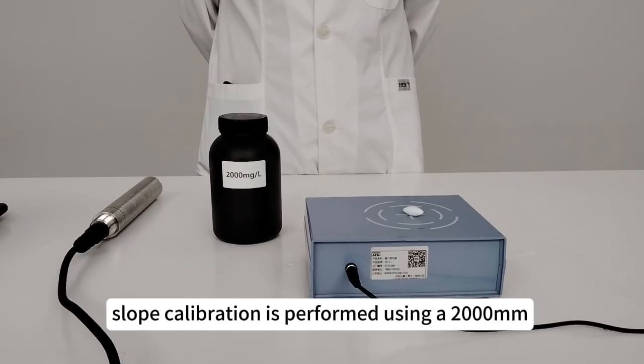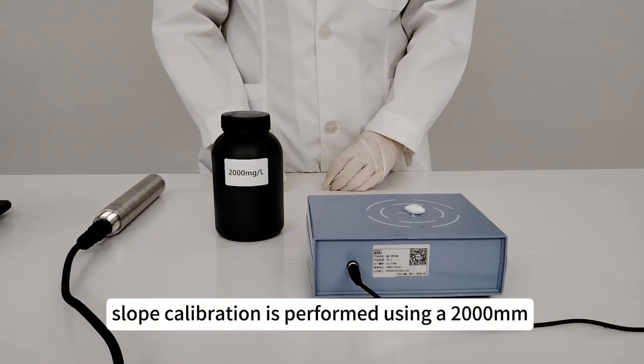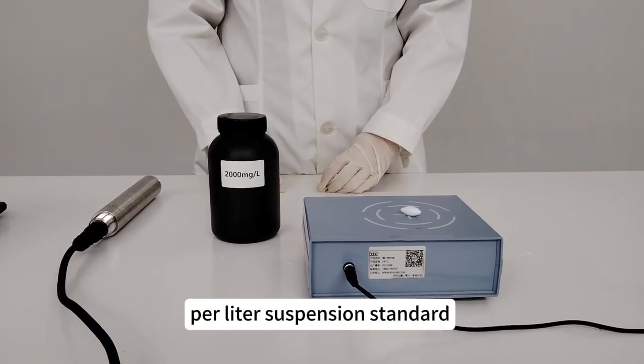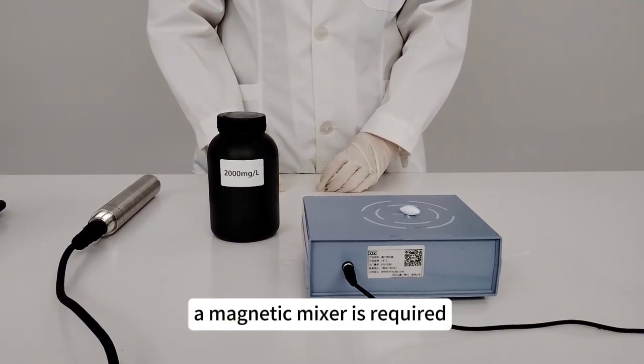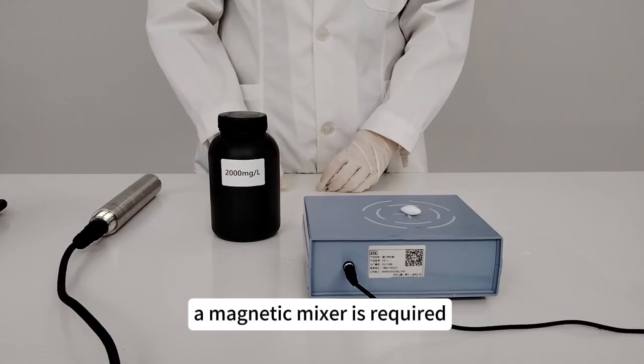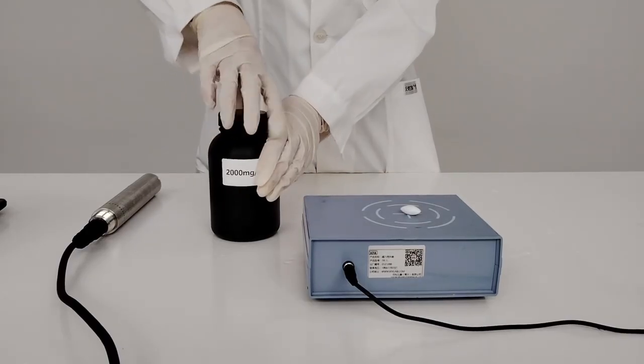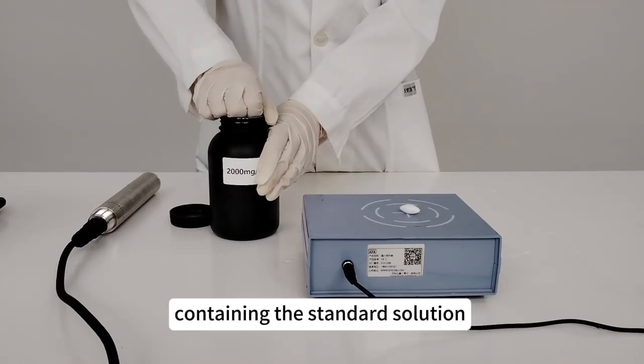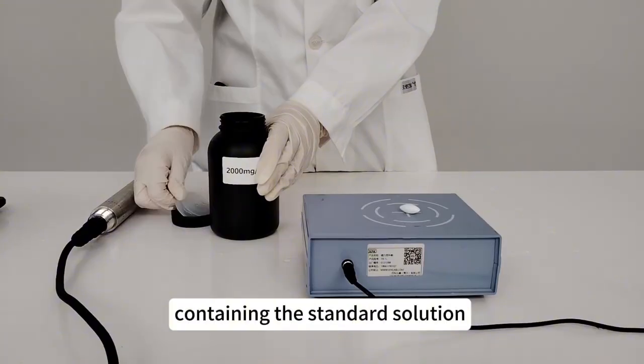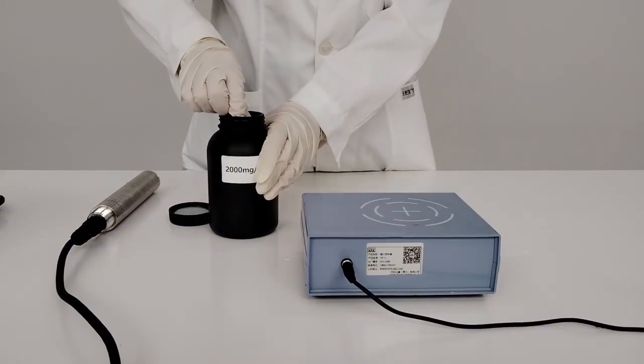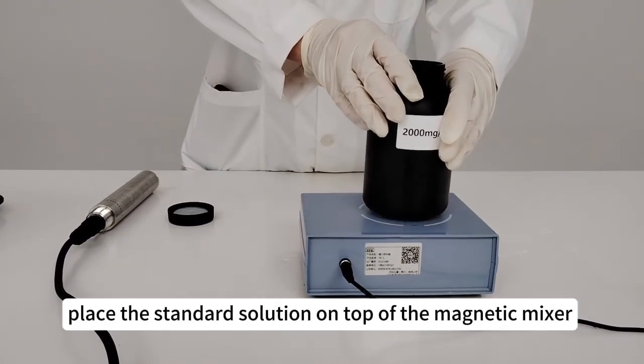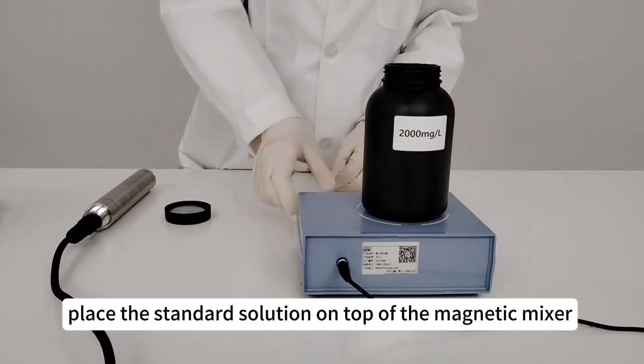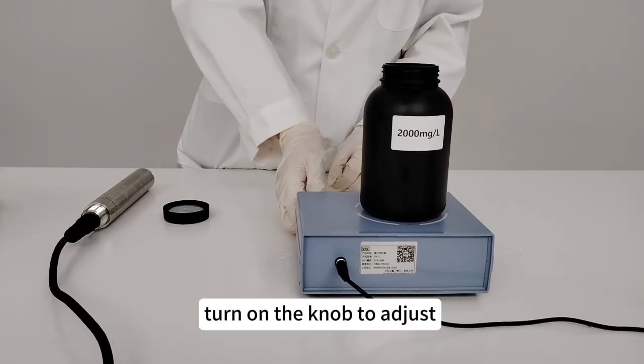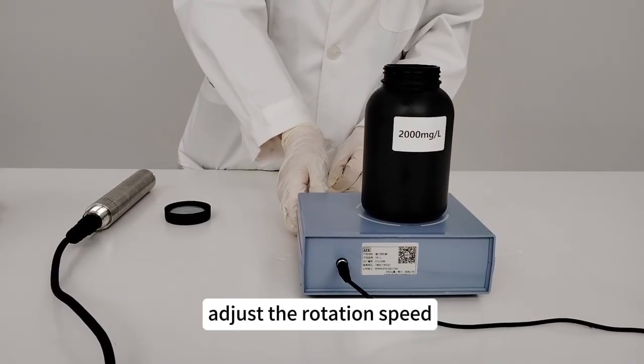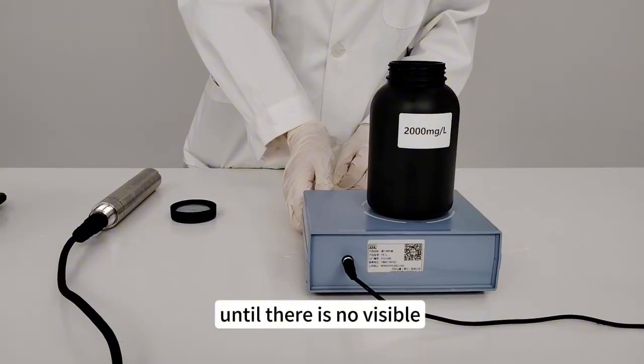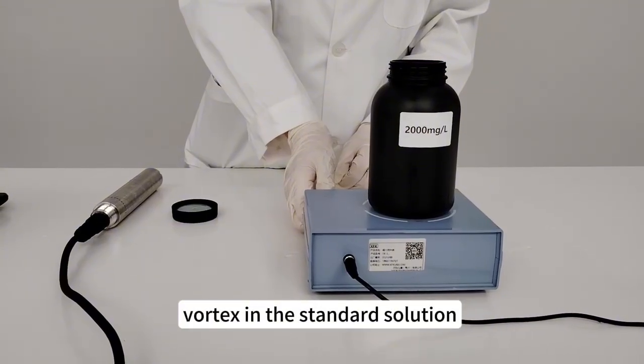Slope calibration is performed using a 2000 milligrams per liter suspension standard. A magnetic stirrer is required. Place the rotor in the bottle containing the standard solution. Place the standard solution on top of the magnetic stirrer. Turn on the knob to adjust. Adjust the rotation speed until there is no visible vortex in the standard solution.